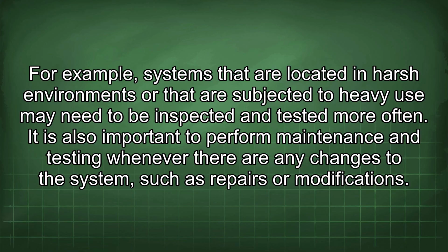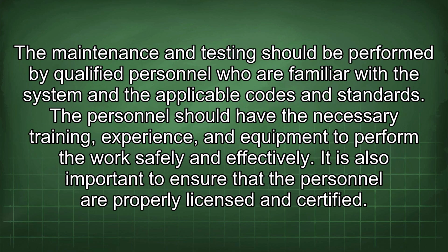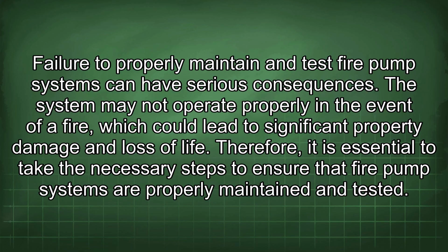It is also important to perform maintenance and testing whenever there are any changes to the system, such as repairs or modifications. The maintenance and testing should be performed by qualified personnel who are familiar with the system and the applicable codes and standards. The personnel should have the necessary training, experience, and equipment to perform the work safely and effectively. It is also important to ensure that the personnel are properly licensed and certified. Failure to properly maintain and test fire pump systems can have serious consequences. The system may not operate properly in the event of a fire, which could lead to significant property damage and loss of life. Therefore, it is essential to take the necessary steps to ensure that fire pump systems are properly maintained and tested.